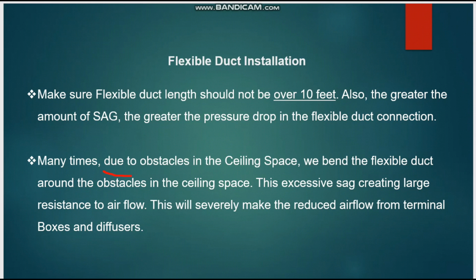And many times, due to obstacles in the ceiling space, we bend the flexible duct to the side. Okay, this happens because the HVAC duct is clashing with other services. At that time we will slightly bend the flexible duct. So this excessive sag creates large resistance to airflow. This will severely reduce the airflow from the terminal box and diffuser. So this is the important thing.